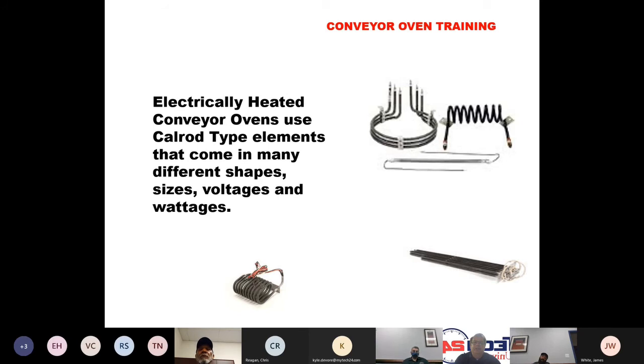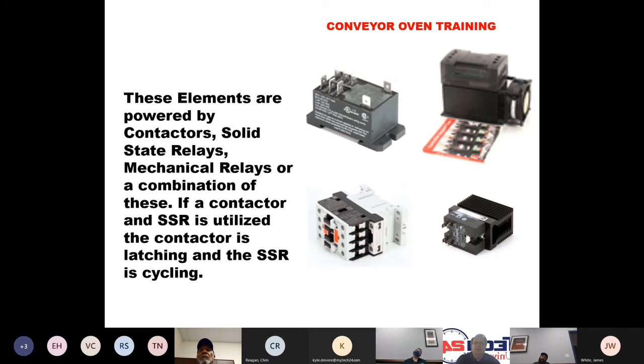Electrically heated conveyor ovens use Calrod type elements. They come in many different shapes, sizes, voltages, and wattages. The elements have to be powered by a contactor, a solid-state relay, a mechanical relay, or a combination of these. Typically, if there's a contactor, there'll be an SSR that's also utilized. The contactor acts sort of as a latching contactor. Then the SSR will do the cycling.